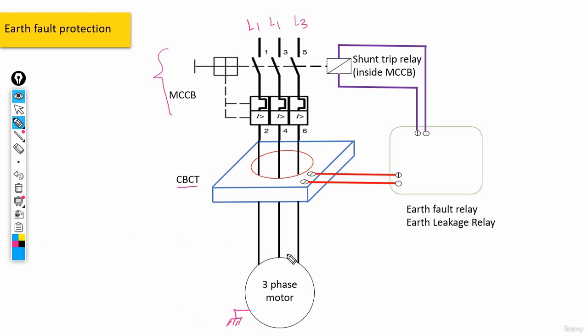Alright, back to our discussion, guys. Let's say for any reason, a fault current has been created. In other words, we have an earth leakage. In this case, a very small current would be created in between the motor's frame and the earth. Now, because of this current leakage, we would get a signal on both sides of our CBCT transformer. Now, the CBCT transformer would be connected to this relay called the earth fault relay.